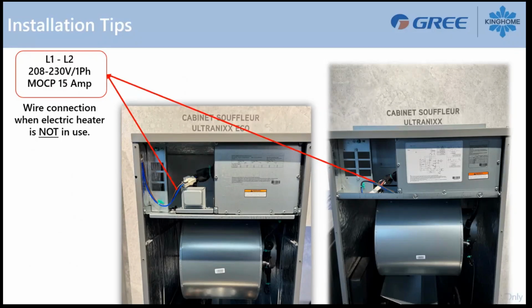On the electrical side, when you open the front panel here, what you will see between a KU and a KD air handler are those black and brown wires here. They are your high voltage connection if you do not install an electric strip. So if you're using the air handler without electric strip, you need to keep this wired connection here. This Molex is already plugged, and then you just have to do your wire connection directly here. So it will be a 15 amp 240 volt connection directly on the wire like this, and that will be good for an installation without duct heater.